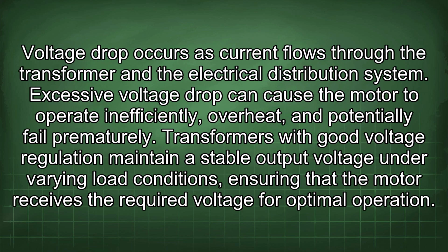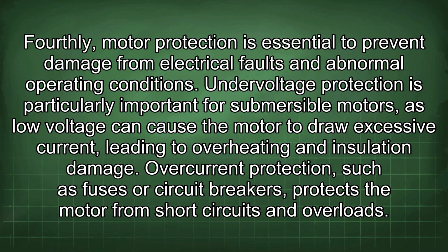Voltage drop occurs as current flows through the transformer and the electrical distribution system. Excessive voltage drop can cause the motor to operate inefficiently, overheat, and potentially fail prematurely. Transformers with good voltage regulation maintain a stable output voltage under varying load conditions, ensuring that the motor receives the required voltage for optimal operation. Fourthly, motor protection is essential to prevent damage from electrical faults and abnormal operating conditions.